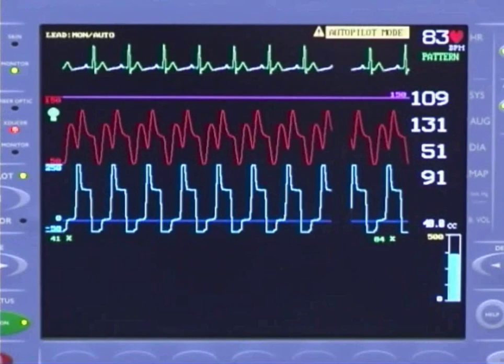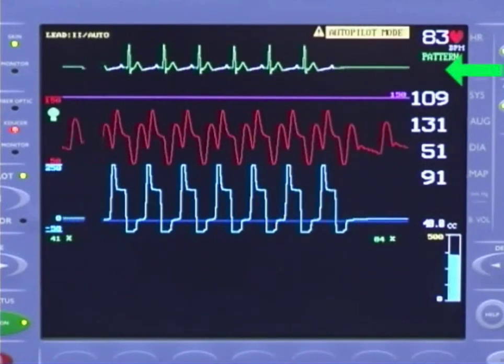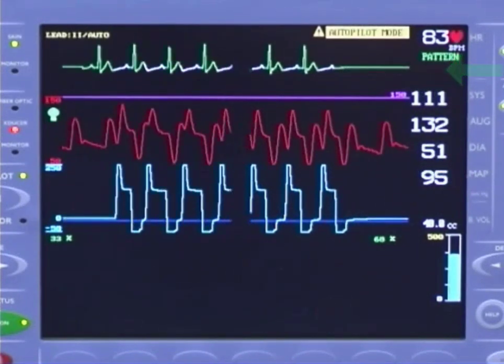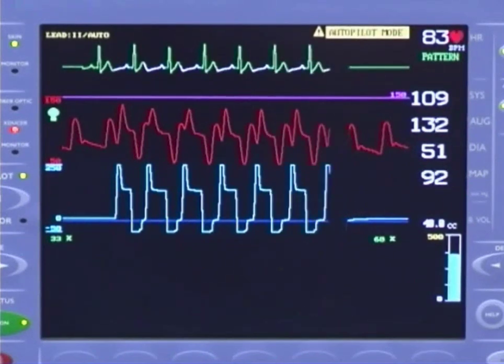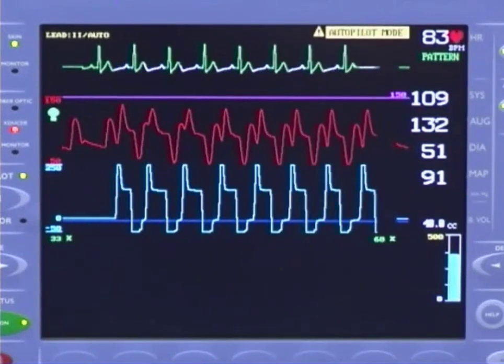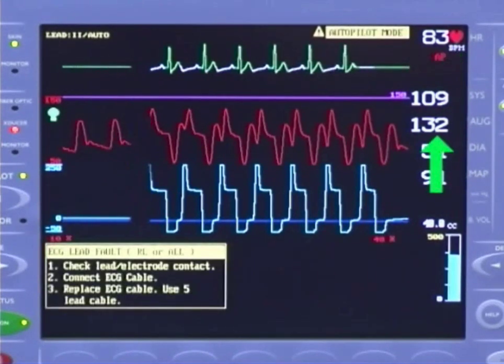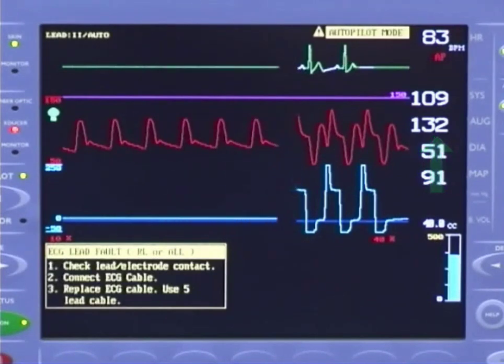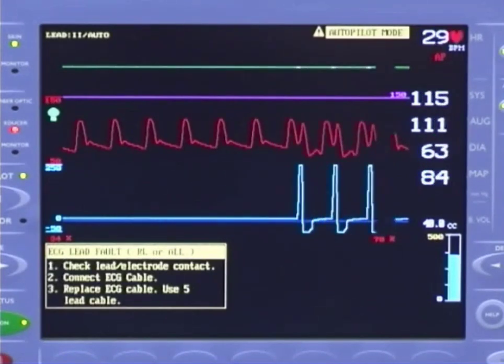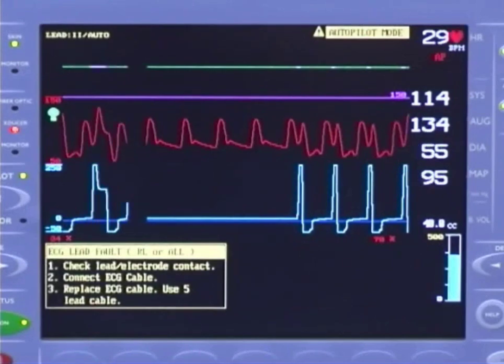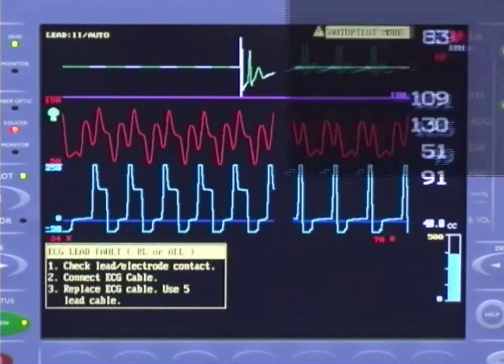For example, if the current lead is lost or becomes noisy, AutoPilot automatically switches to a more stable lead to maintain a consistent trigger. If all ECG leads and/or sources are lost, AutoPilot utilizes the arterial pressure waveform as the trigger. When the ECG is reestablished and stable, an ECG trigger is automatically resumed.